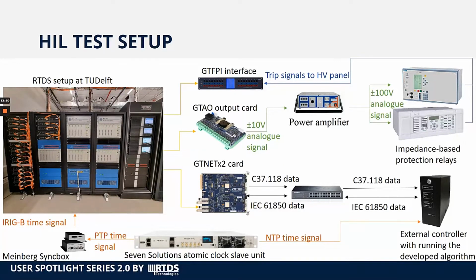As for the developed protection algorithm, it was set to run in an external controller which receives C37.118 PMU data from the GTNet X2 card and sends back data using IEC 61850 to the RTDS simulator. This setup has to be time synchronized, and for this our lab incorporates an atomic clock slave unit which synchronizes the RTDS and the external controller, so everything is time synchronized.